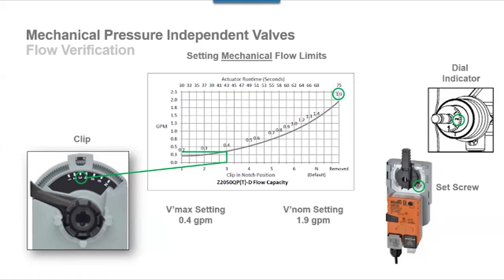Accomplishes the same thing. Some of our older product from back in 2003, these settings were done with electronic stops programmed in the actuator. But in all these cases, it's all field adjustable. They can be factory set, but they can also be field adjusted. So there is no big change that needs to be made if you want to adjust these.